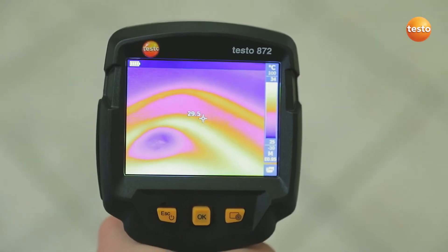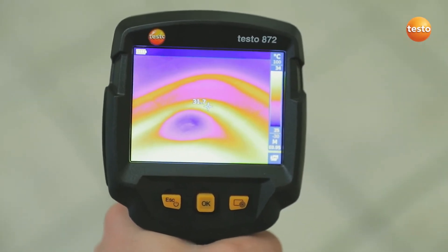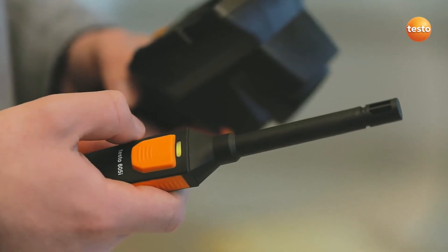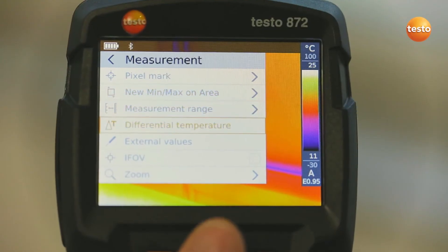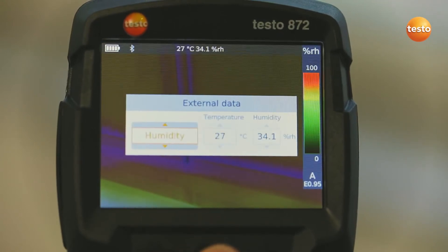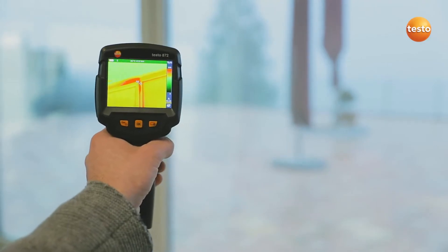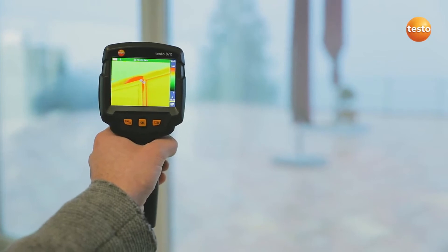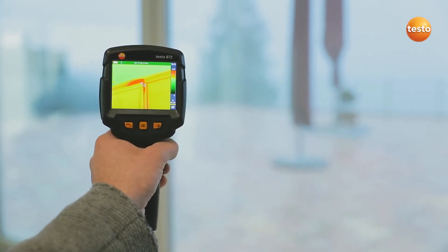The Testo 872 also allows you to see at a glance whether the underfloor heating is still working correctly. In order to detect mold better, the imager integrates the air humidity and temperature values measured with the thermohygrometer Testo 605i into the image. In combination with the thermal imager's special humidity palette, this enables you to identify mold risk really easily, based on the traffic light principle. Here, the traffic light is red — that means acute mold danger for this measurement object.